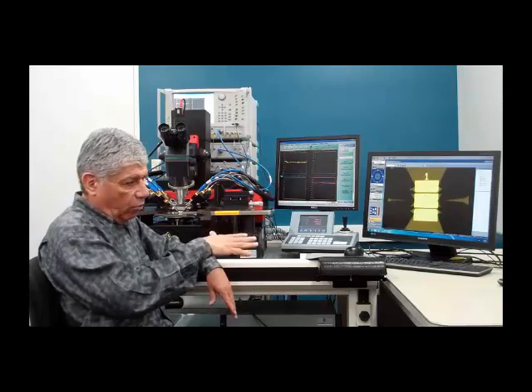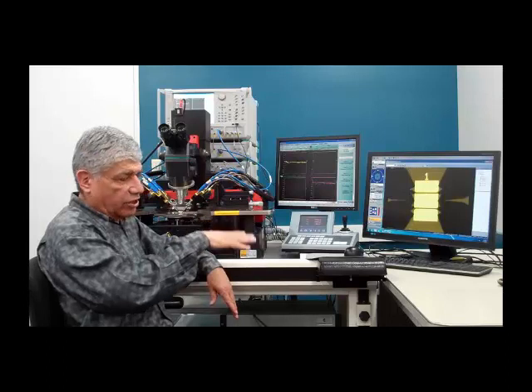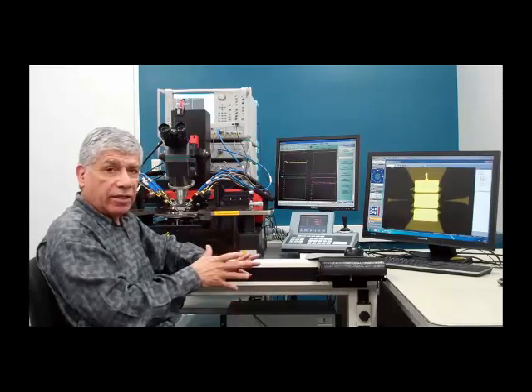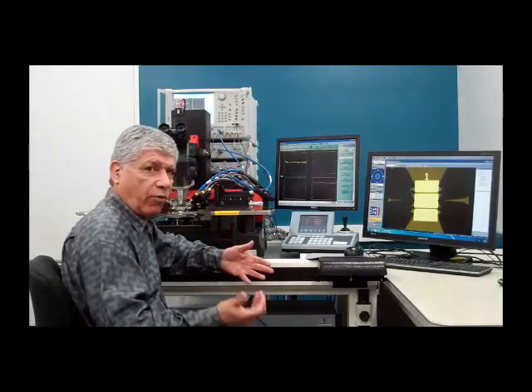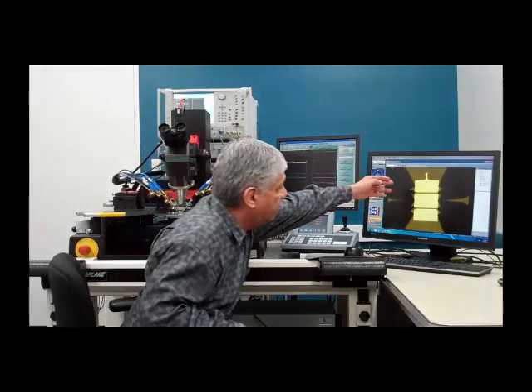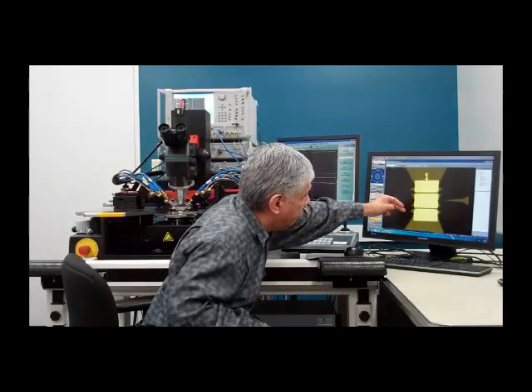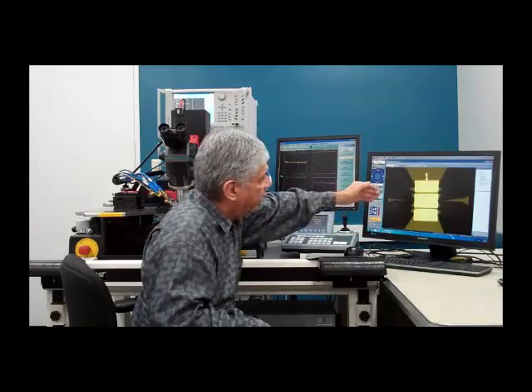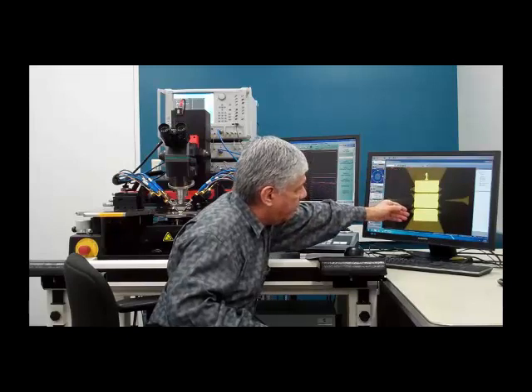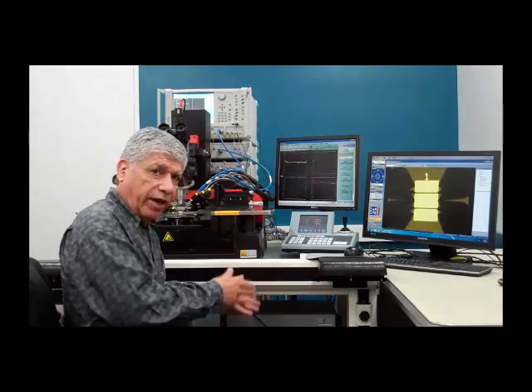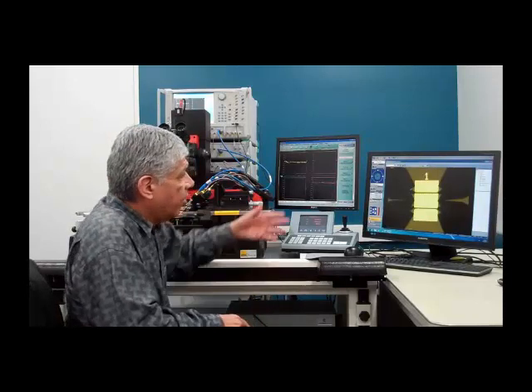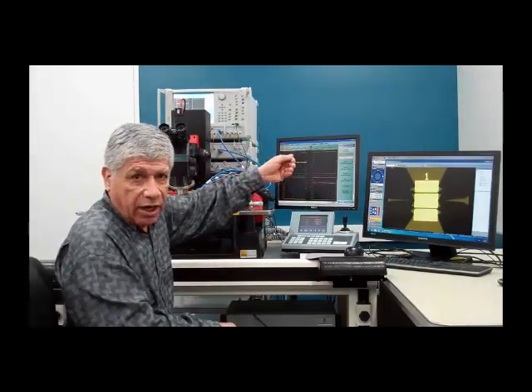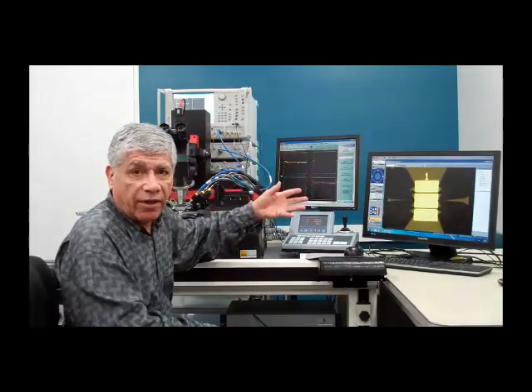So in other words, you don't have one edge or one side touching down before the other and creating an imbalance in the ground contacts, especially when you get into the differential probing environment, because as you can see, your ground signal is quite a wide stretch. And if I'm touching down on this ground and barely touching here, I end up with a poor ground for my signals. And that could be one of the issues in your final calibration results or even measurement results. So you want to set the probes up properly, and you may want to touch down on other pads that are not as important to verify that the touchdowns are correct and everything is in proper alignment.